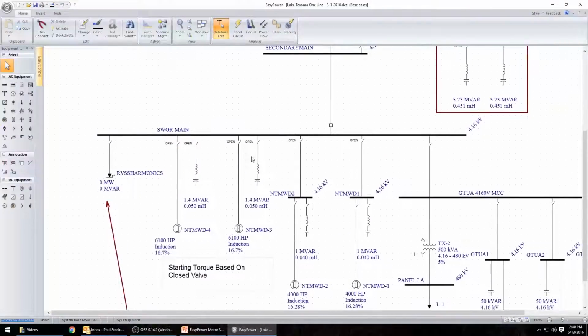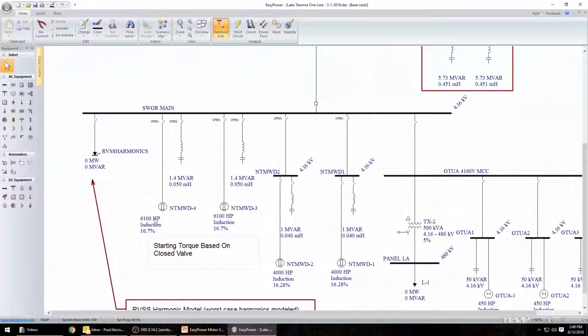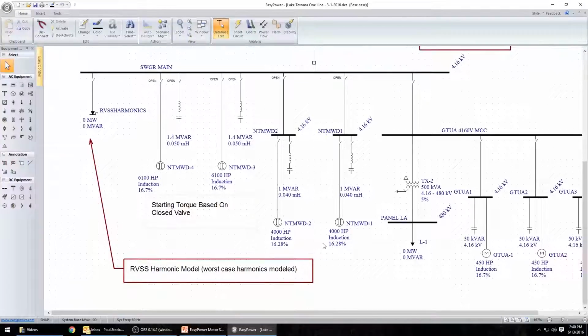The customer's main bus, and this is a pump station for a water pipeline that has 4 very large motors, two 6100 horsepower motors. These are new motors, and two 4,000 horsepower motors. The 4,000 horsepower motors have some capacitors connected to the terminals for power factor correction, and these reactors actually just represent 40 microhenry reactors that are typical for capacitor bank application. They will not influence the reactive output of that capacitor in any way.